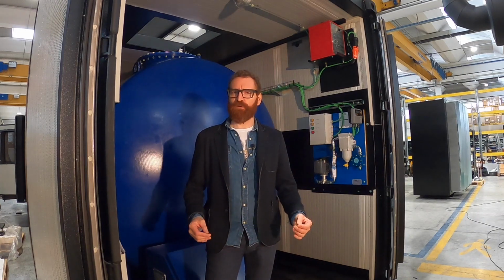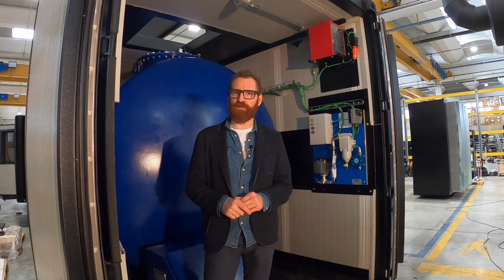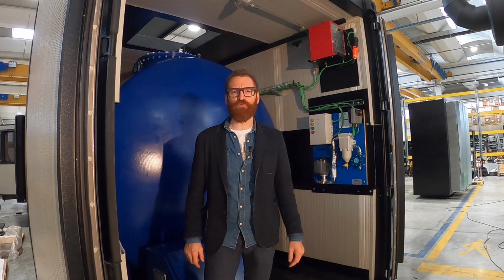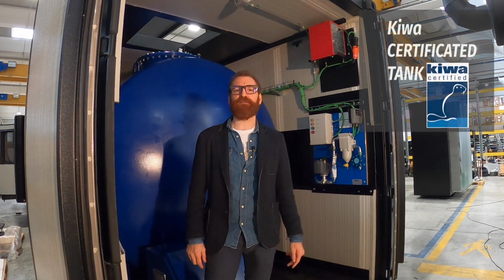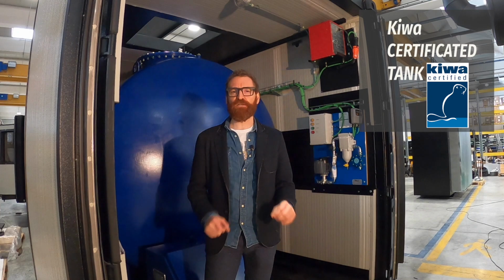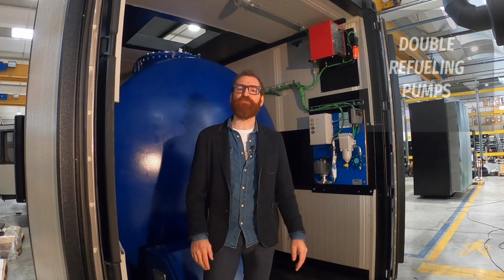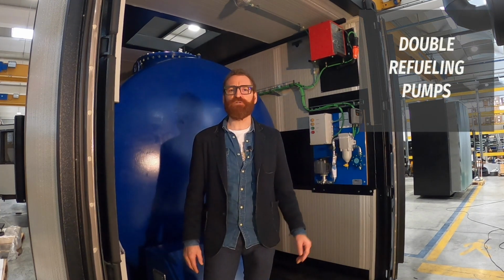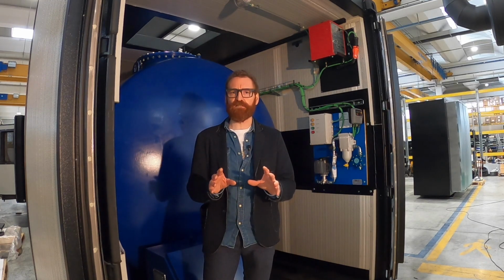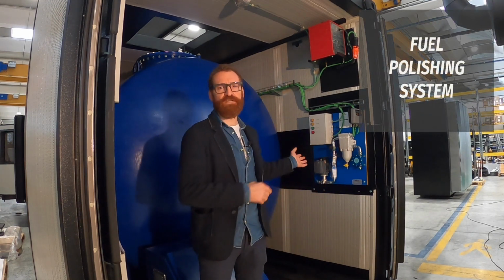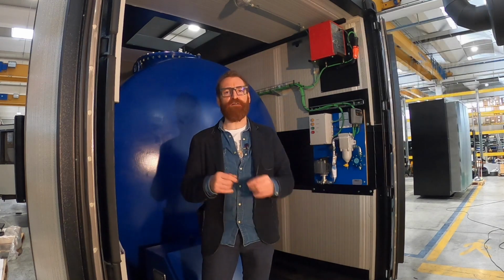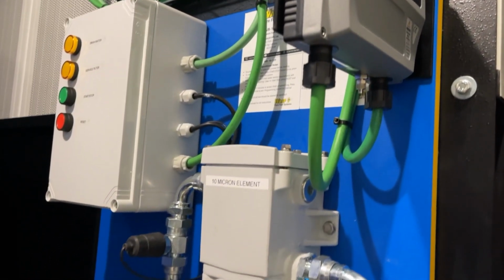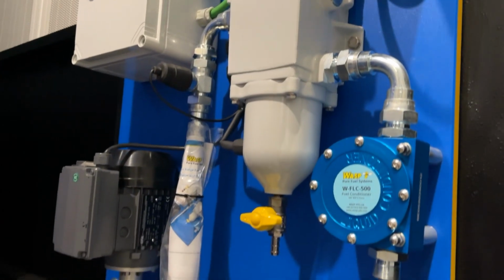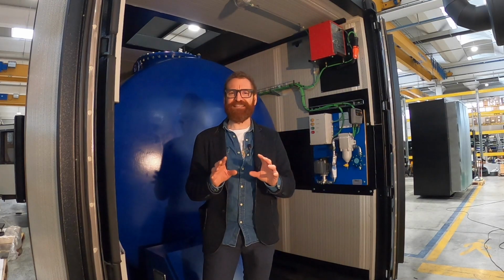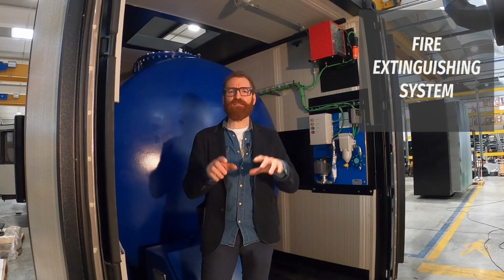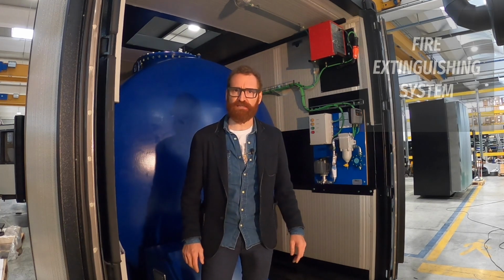According to the project, we used special components, such as special double-walled tanks complying with Kiwa standards, a special double set of fuel refilling pumps to permit a redundant system, and a special polishing filter system which avoids the further development of sludge in the fuel. Furthermore, we created dedicated rooms to house an installed fire extinguisher system.